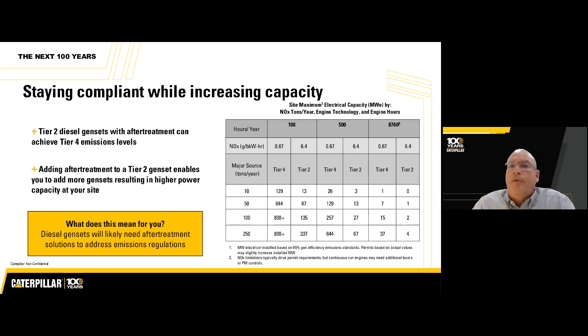As you can see in the table on the right, you can install significantly more power per site utilizing engines meeting Tier 4 emission levels than you can using Tier 2 engines without aftertreatment, regardless of your site's attainment status. As discussed earlier, do keep in mind that emergency use engines can only be operated for specific reasons and durations outside of the loss of grid power.